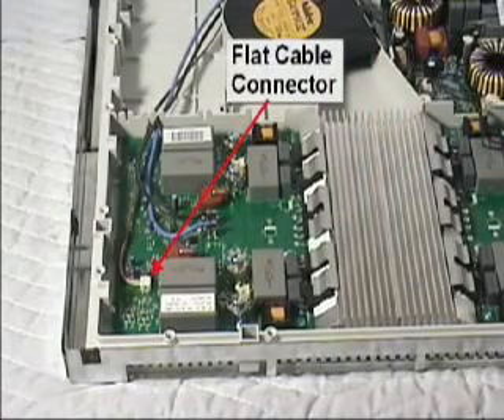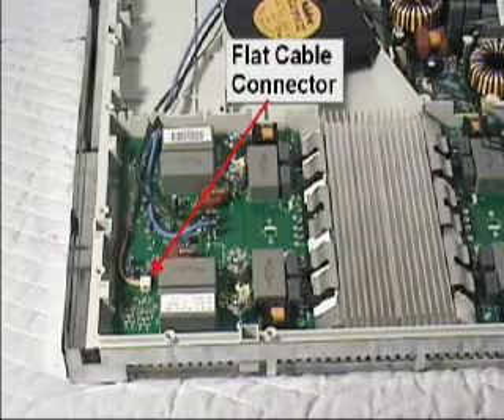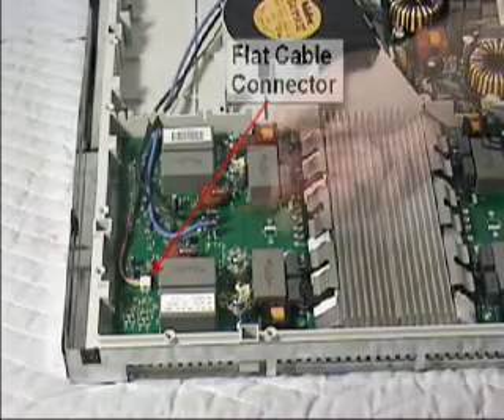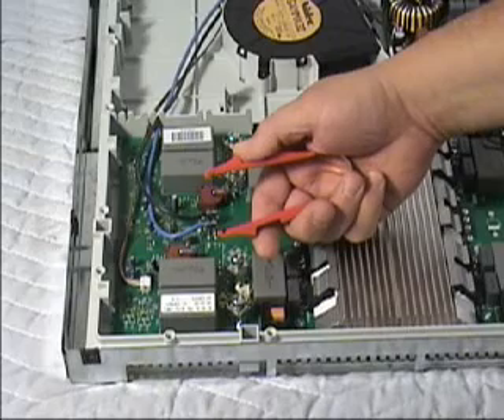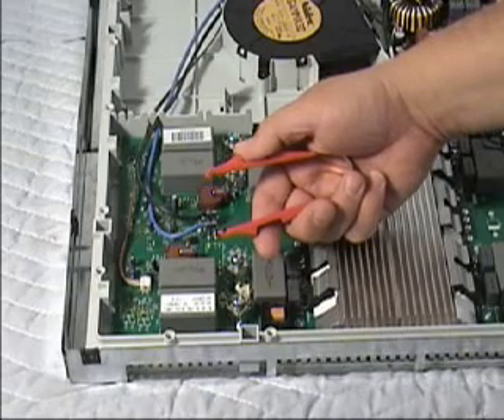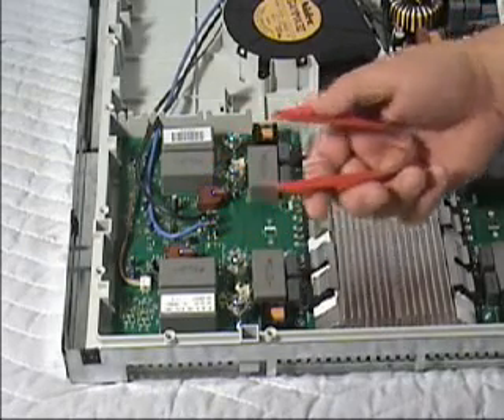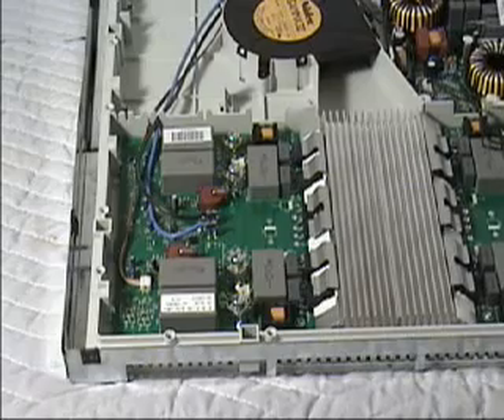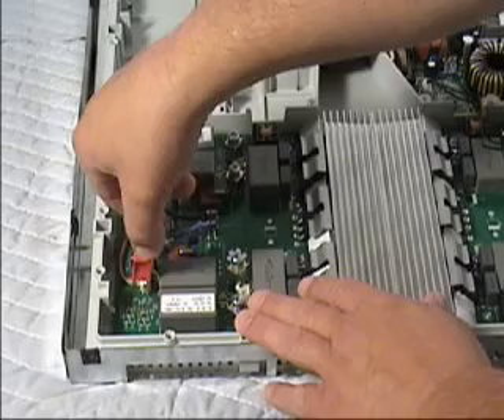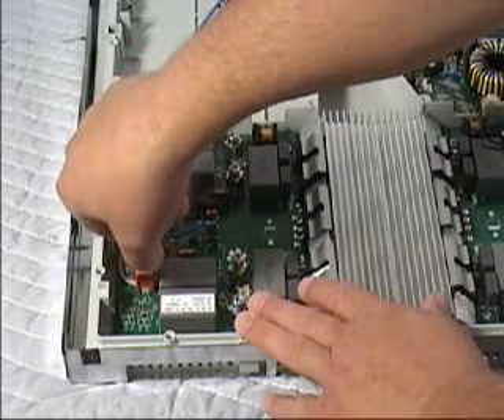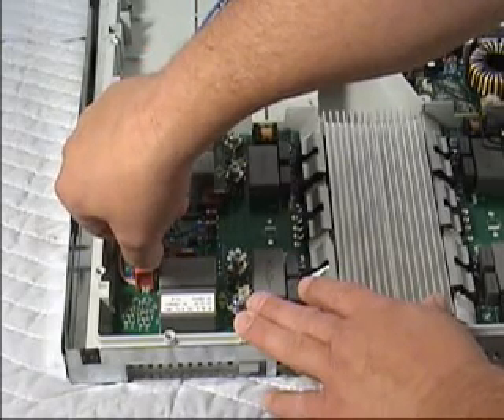To unplug the flat cable connector on the filter board and the power generator board, use the special cable removal tool. This tool is packaged with each replacement power board and filter board, as well as with the replacement cable. Grip the connector with the tool as shown and pull up to release the connector.